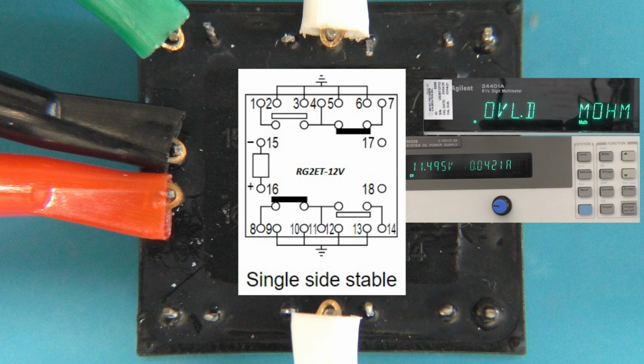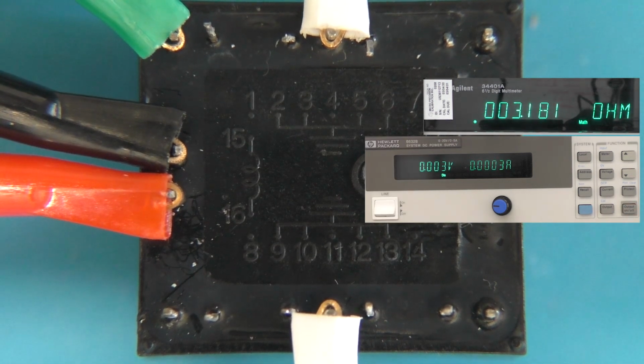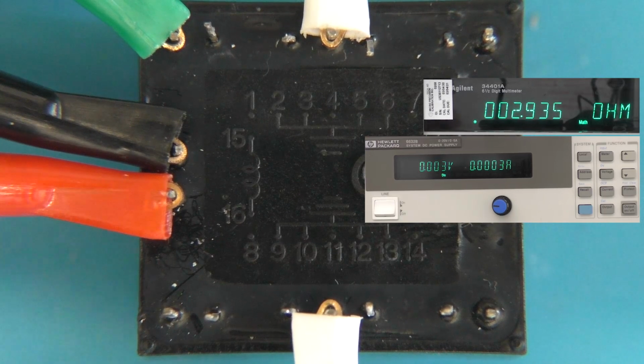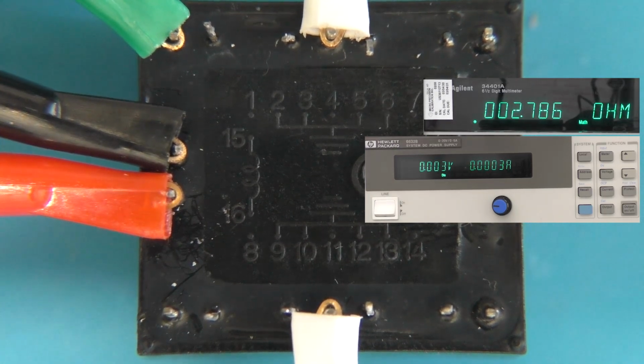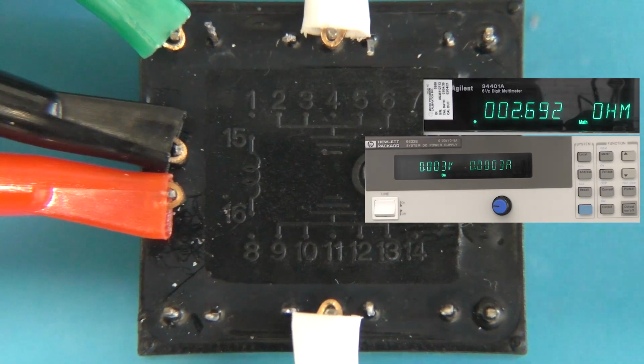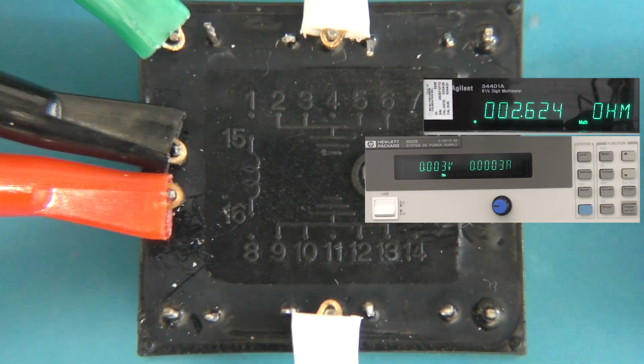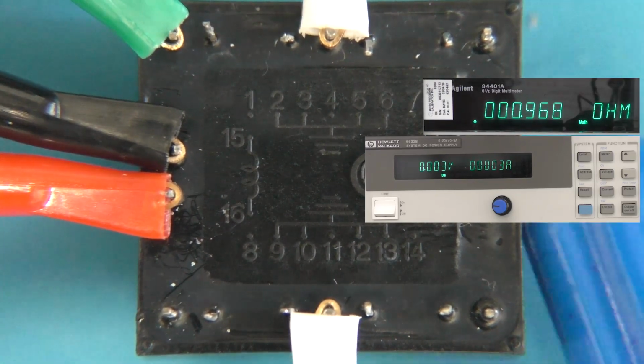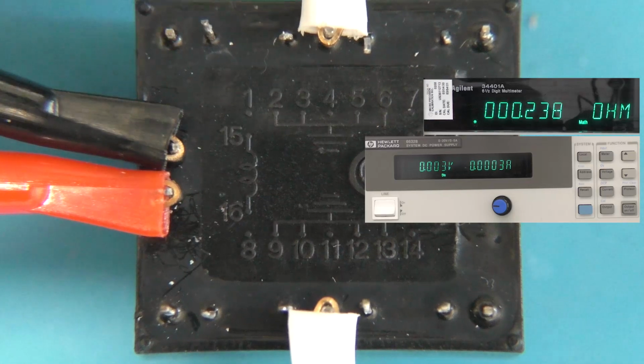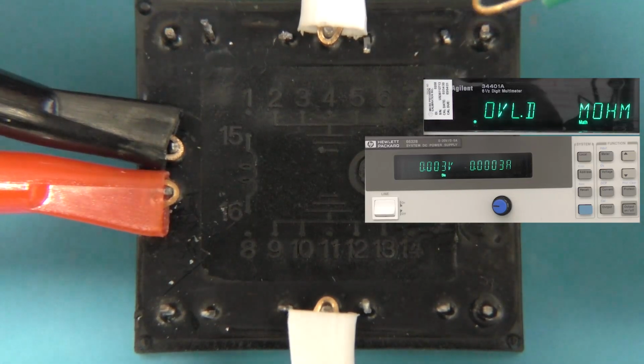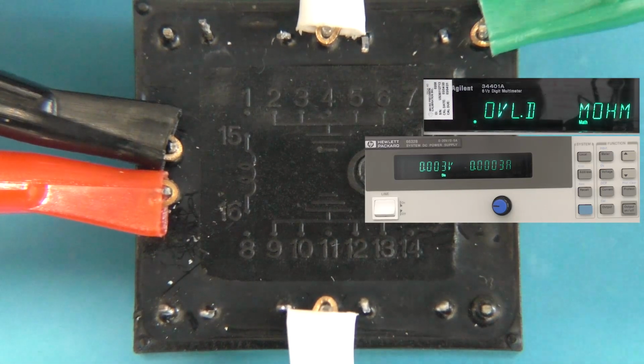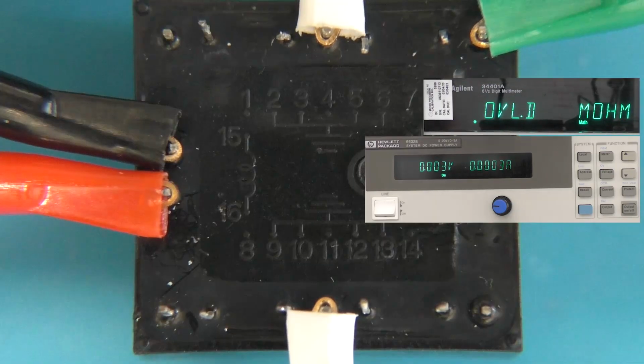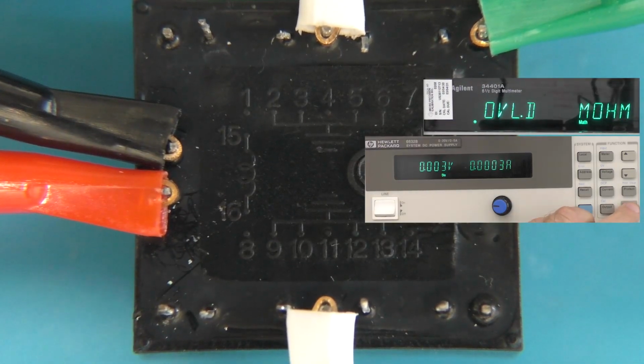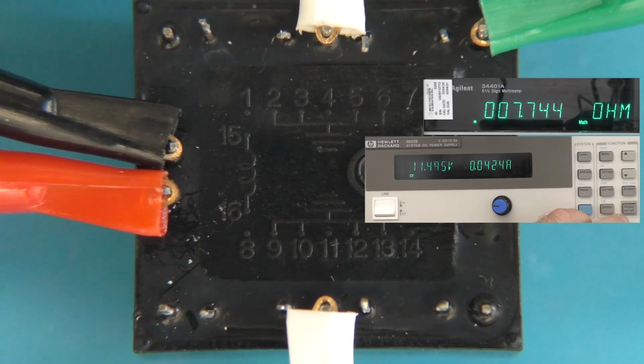Let's continue the test. Remove the power. Note the resistance on pins 1 and 4 is now around 3 ohms. Clearly this relay is sick. We give it a light tap. The resistance drops to 0.1 ohms. We move the green clip to pin 7. Pin 7 should be the normally closed pin, but clearly this is open. Apply power, the pole closes on pins 4 and 7 and we see around 7 ohms.